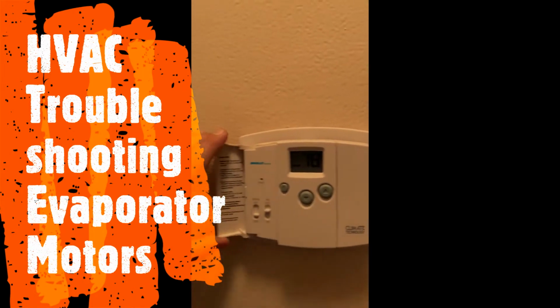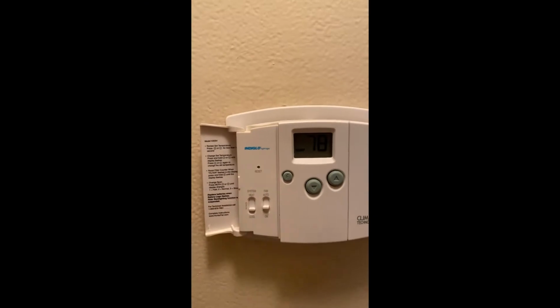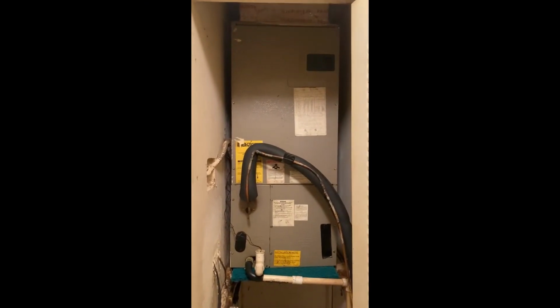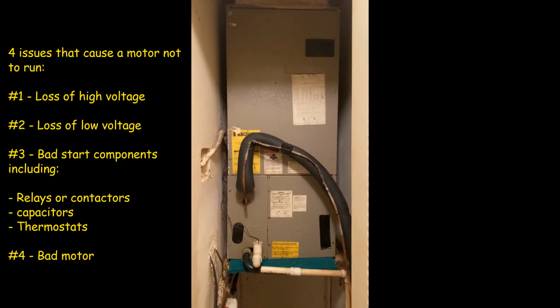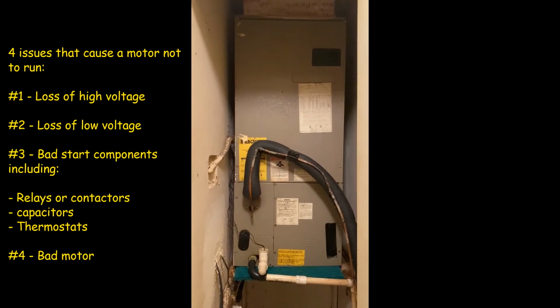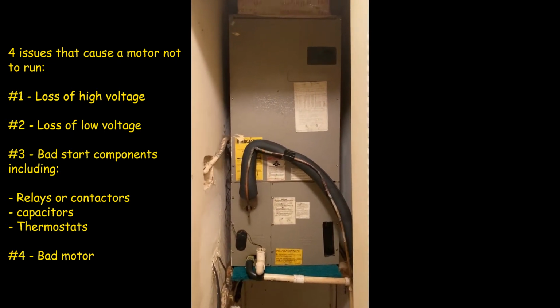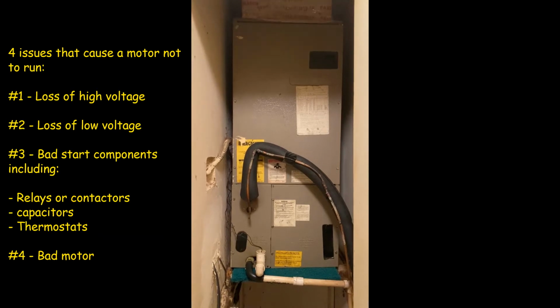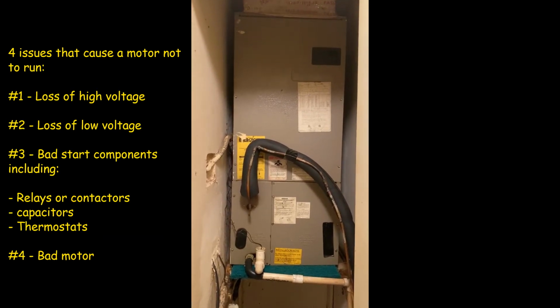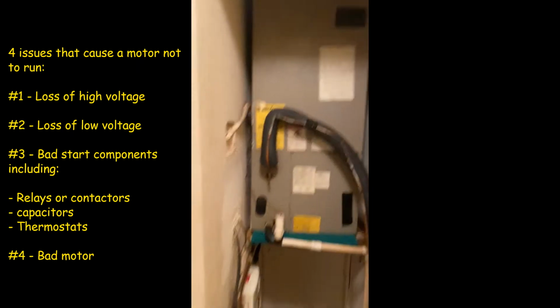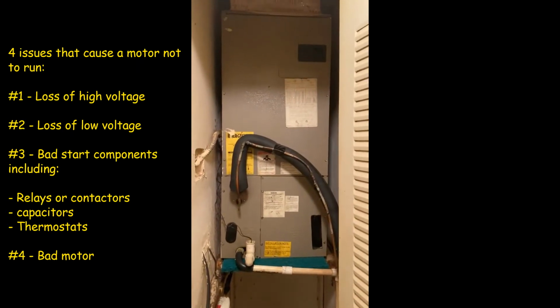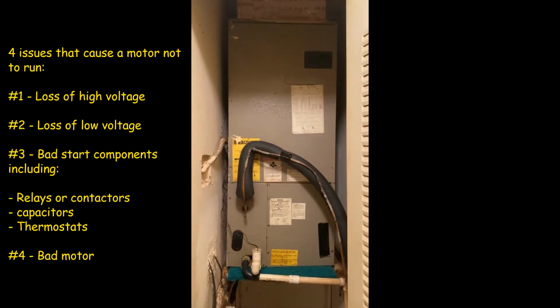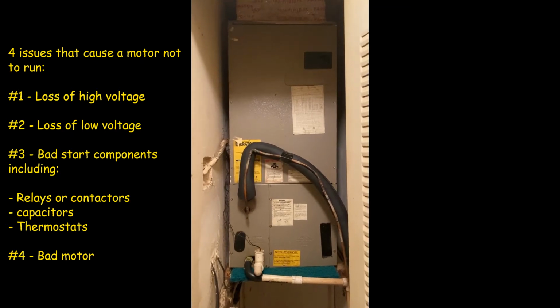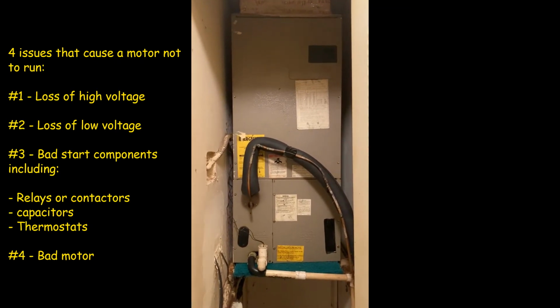So if you're looking at this video, you had an issue with your evap motor, meaning you put it on and it just didn't turn on. There's 4 things that can cause an evap motor to not run. Number 1 is no high voltage. Number 2 is a loss of control voltage or low voltage. Number 3 is your start component, like your relays or contacts. And number 4 is a bad motor.